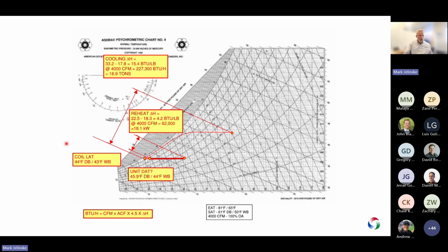We can do this with a heating coil, but that's going to require a bunch of energy. It's actually about 27%. See, there's that delta H, the difference in energy level between what's coming off the supply fan and what we want to come out of the unit. It still requires an add of heat, and it's about 27% of what we just took out with the cooling coil. You know, besides being bad form, it's illegal according to the energy codes.